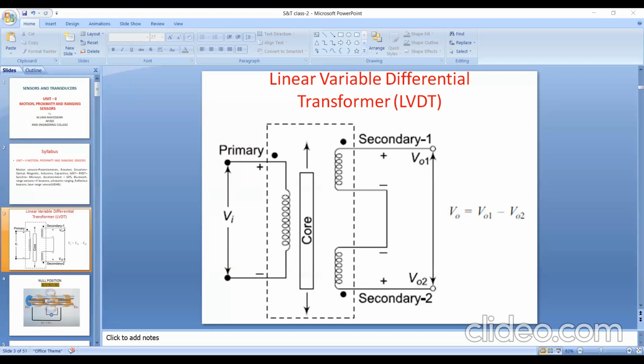Now the second case: the core is moved towards the right of the null position. The magnetic flux linkage with ES2 will be more than that of ES1. So the output voltage E0 is given by the differential voltage, ES1 minus ES2, and it is out of phase with the primary winding. The amount of voltage in either secondary winding is proportional to the amount of movement of the core. However much the voltage differential is, that is equal to the displacement of the core. So with respect to the linear motion, we are able to obtain the voltage magnitude. Here E0 is equal to ES1 minus ES2. Since ES2 is greater, we obtain a negative voltage value.